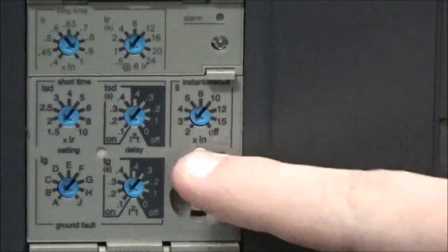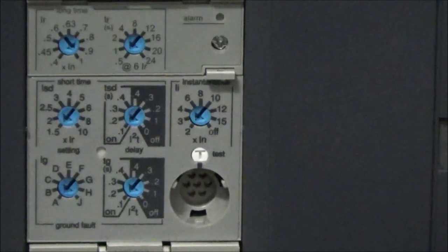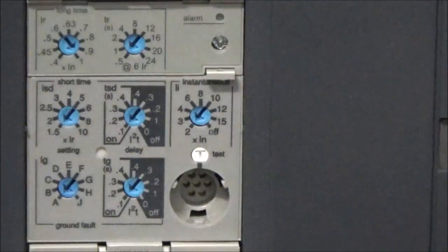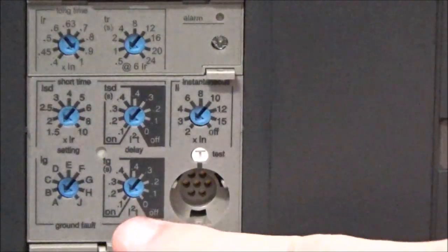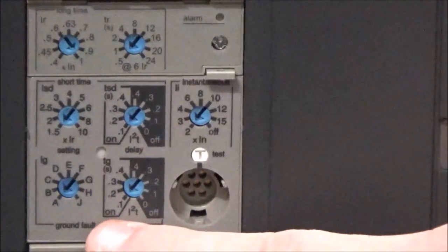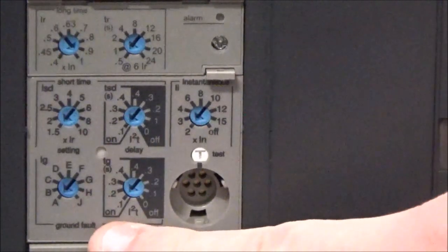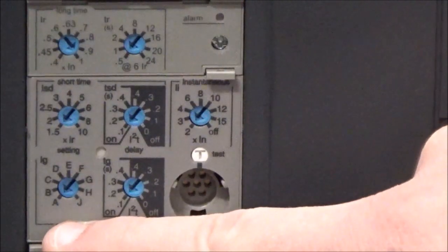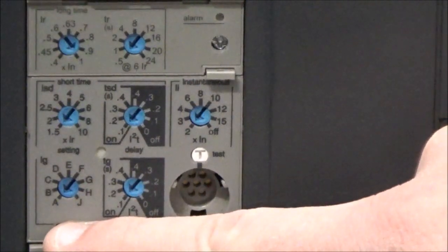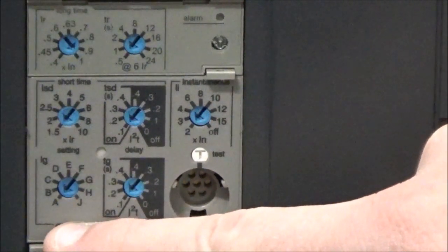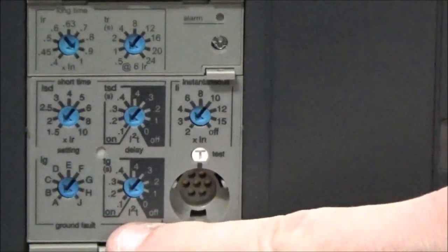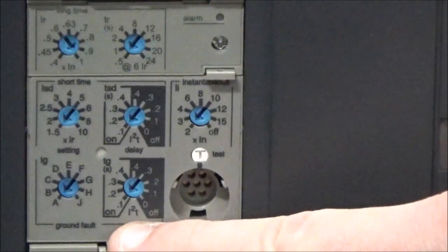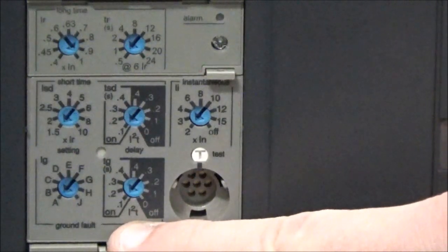Now on MicroLogic 6.0 trip units you will have two additional dials for ground fault. You'll have the IG, which is the ground fault trip point, and you'll have the TG, which is the ground fault delay setting.